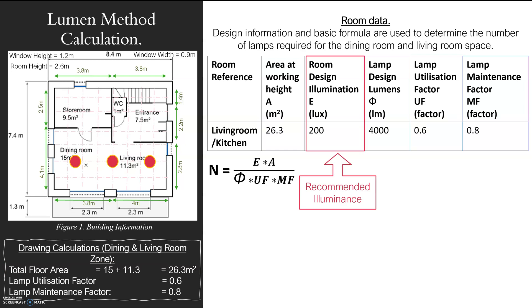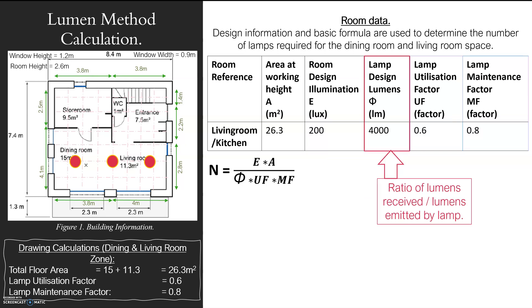Room design illumination is the illuminance that is recommended — how much lighting you're supposed to have in that living room or kitchen. I get that from CIBSE, the Chartered Institute of Building Services Engineers. They have all the recommendations, but you can go elsewhere. The key question is: what lux level do you want on that surface when working on it? Recommendations from CIBSE are always a good reference.